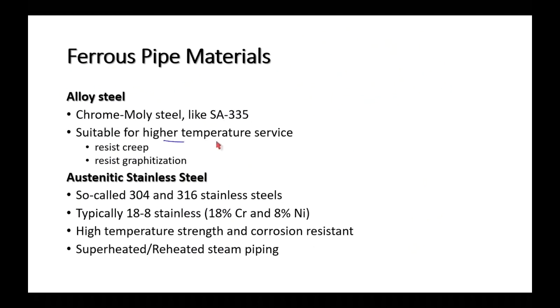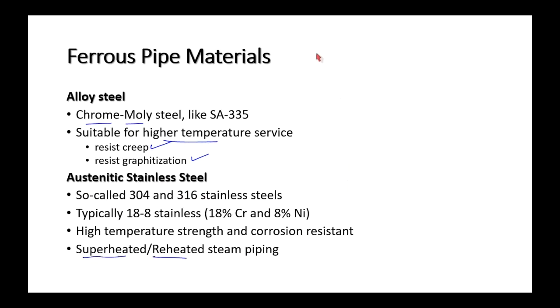For higher temperature service, we use alloys — commonly chromoly steels, which are creep-resistant and resist graphitization. There are also austenitic stainless steels used at high temperature for superheaters and reheaters. Austenite is face-centered cubic (FCC) as opposed to ferrite, which is body-centered cubic (BCC).